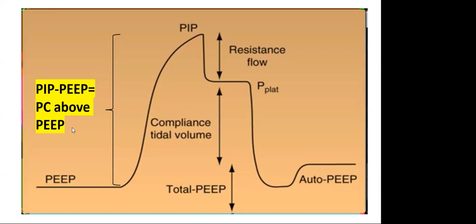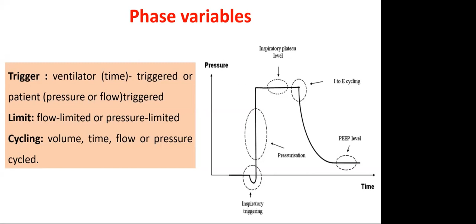The more common things which you have to know for any setting: the ventilator is a machine, so you have to tell the ventilator when to trigger, and how much pressure or volume it can give at maximum. Okay, a limit should be there, and when it has to change over, cycling should be done from inspiration to expiration. So the trigger: what causes the breath to begin? It can be machine controlled. The ventilator will trigger regular breaths at a frequency which depends on the set rate, or it is patient assisted, where the patient has started triggering, then the ventilator will take over in some settings.